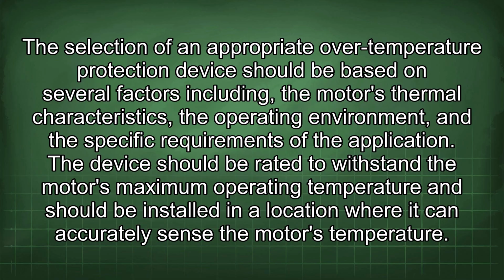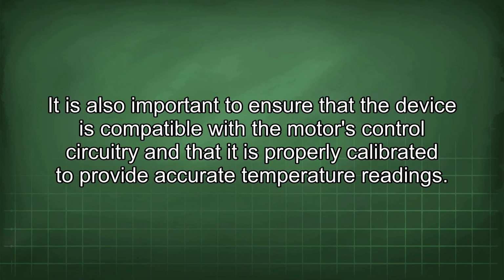The selection of an appropriate over-temperature protection device should be based on several factors, including the motor's thermal characteristics, the operating environment, and the specific requirements of the application. The device should be rated to withstand the motor's maximum operating temperature and should be installed in a location where it can accurately sense the motor's temperature. It is also important to ensure that the device is compatible with the motor's control circuitry and that it is properly calibrated to provide accurate temperature readings.